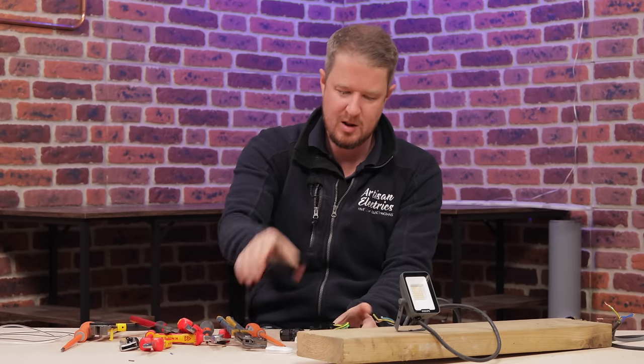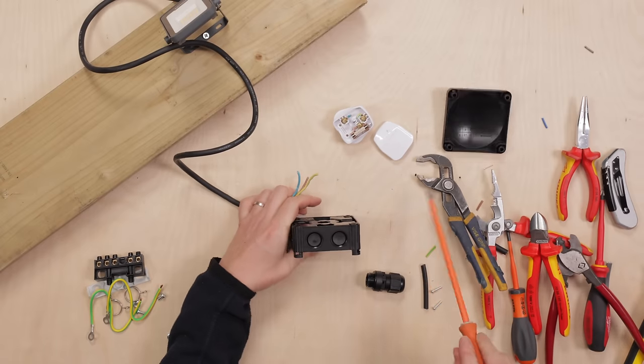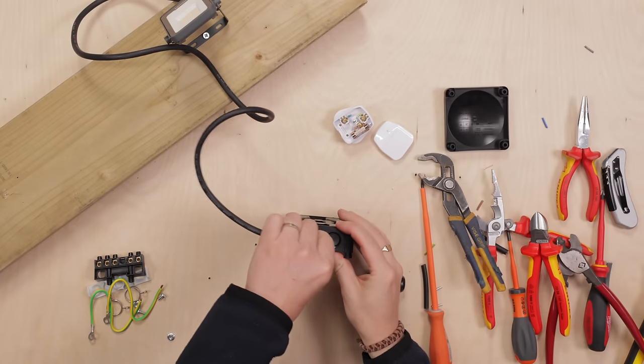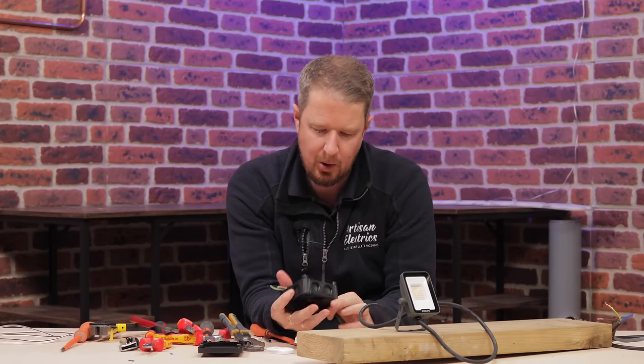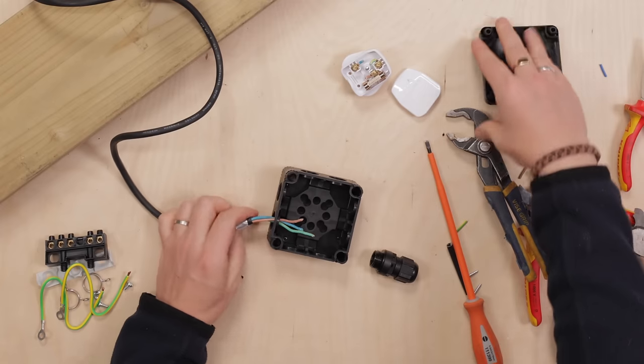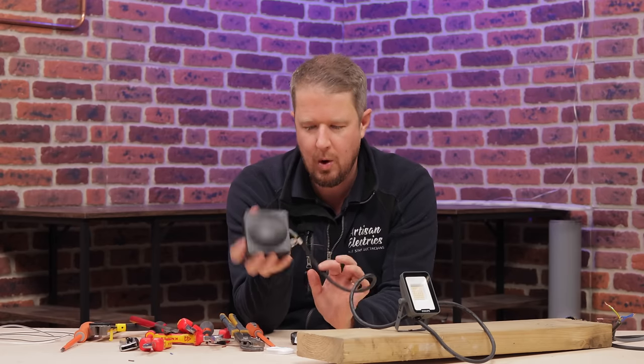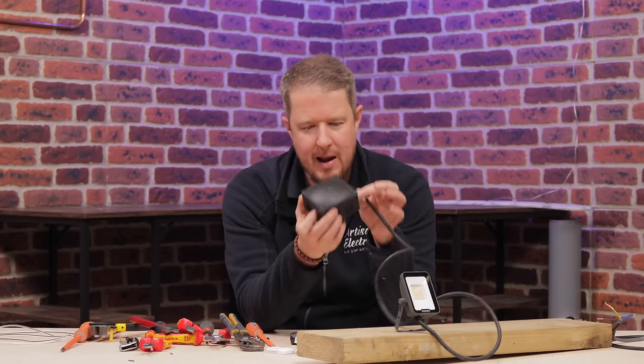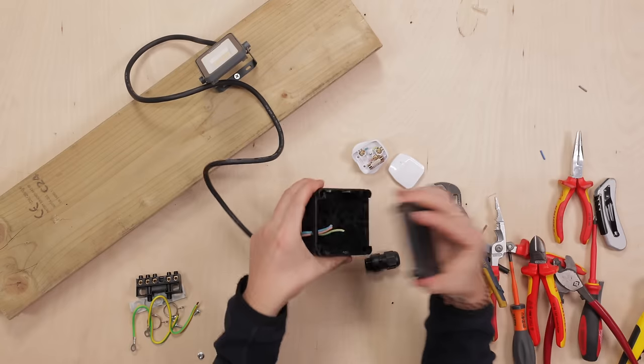When wiring up a junction box like this. There's two ways that they often do it. They'll either punch a hole in it like that and just shove the wires through. Now the problem with that is there's no cord grip there so you can easily pull the wire out. But the other thing that we often see is it's like this. Just hanging out of the junction box. Stuff that on the wall and again you've got an issue here with no strain relief and exposed single insulated conductors. Not a good idea.